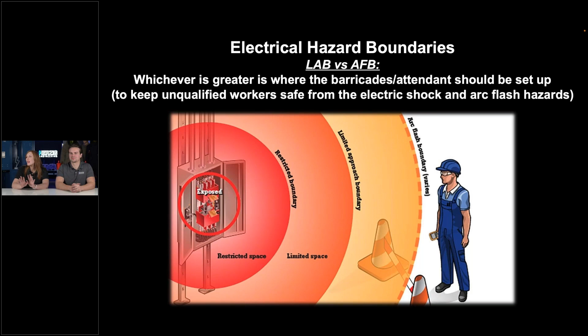Now, exposed. I keep saying this word exposed, hazard exposure. When is equipment exposed? Oftentimes we need to make sure unqualified people know that if they can see metal parts, it's likely exposed. I'm not talking about the enclosure or cabinet, but the pieces, and give them a crash course on what electrical equipment looks like. This is a conductor, this is a terminal, this is a lug, those copper conductors we talked about earlier. Just so they can have a general gut feel of, oh, that's probably exposed, that probably shouldn't be open to where anybody could accidentally touch or approach nearer than a safe distance, per the definition of NFPA 70E's exposed.